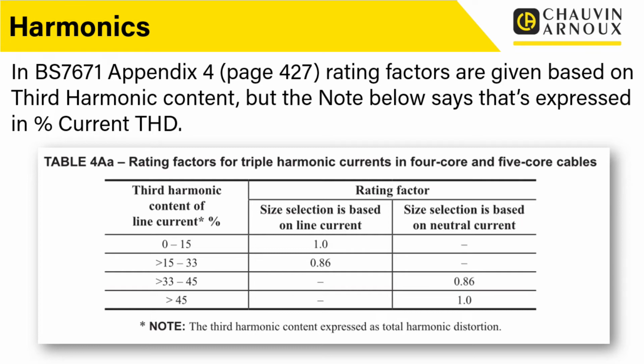So there's a couple of things going on, and like I say, it feels originally like double counting, but I think it's just correcting the design current based on the harmonic currents, and then applying these rating factors on here. And how we decide on the rating factors is based on THD, because to be honest, most people, if you're carrying out a simple measurement, you could do a THD measurement, whereas if you wanted to measure what's just in a certain harmonic, you would need more advanced equipment for doing that. You'd need a PEL, or you'd need a power quality analyzer really to get right into that.